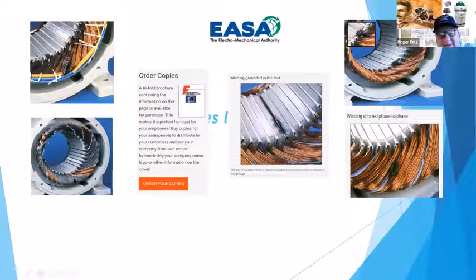This, you can see, because of the rotating field, this had 3 of them because it's 3-phase. So the copper looking color here tells me that this motor was connected delta and Y and lost 1 phase. And so all the power was trying to run through just 2 sets of the phases. And so the motor just became overloaded and over time just cooked itself out.